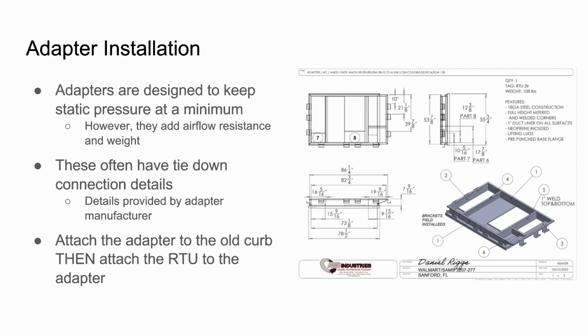The other thing to know is you cannot install an adapter on an adapter. If there's an existing adapter, you need to measure where the supply and return are on the original curb, not on the adapter. I've seen people try it anyway, and it still sort of sets up there, but it's wobbly since the weight is now distributed unevenly, with one side tilted further over than the other.